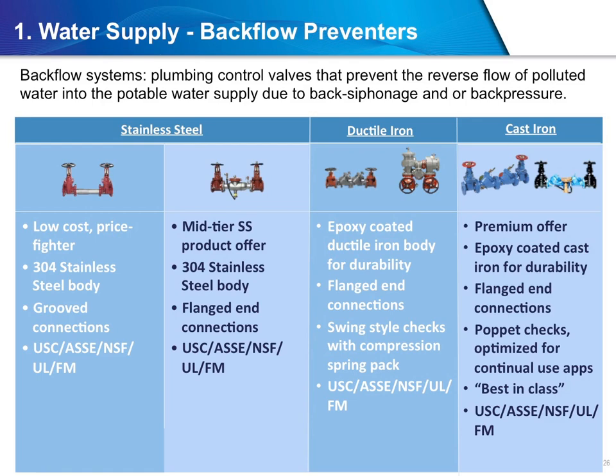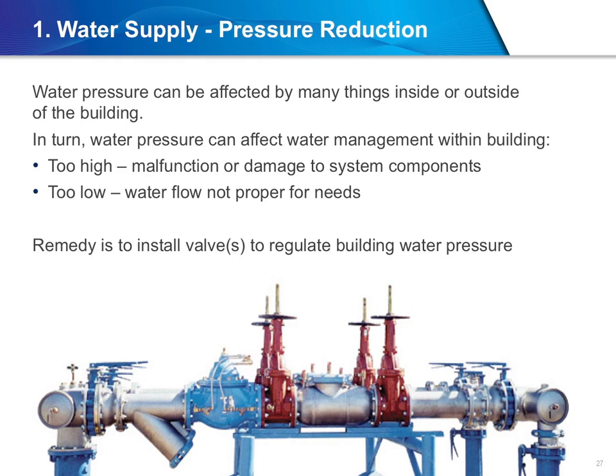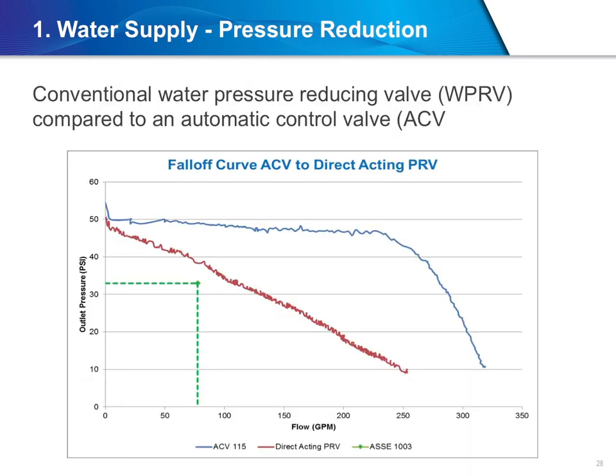One of the things that can alter performance of any water system is the water operating pressure. Water coming in from a municipal system may be affected by other buildings, as well as by the level of demand in a healthcare building. If the pressure is too high, some parts of the building water system may not work well or can be damaged. If the pressure is too low, the water may not flow as intended and may lead to conditions that are conducive to Legionella and other biofilm and bacteria growth. The remedy is to install a valve to regulate the water pressure in the building. There are two fundamental choices in this regard.